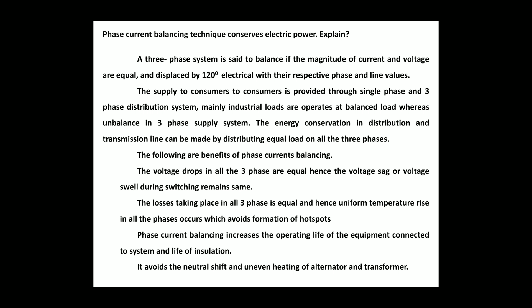The voltage drops in all the three phases are equal, hence the voltage sag or voltage swell during switching remains the same. The losses taking place in all three phases are equal, and hence a uniform temperature rise in all the phases occurs, which avoids formation of hot spots. Phase current balancing increases the operating life of the equipment connected to the system and the life of insulation. It avoids the neutral shift and uneven heating of alternator and transformer. This is the explanation of how the phase current balancing technique conserves electric power.